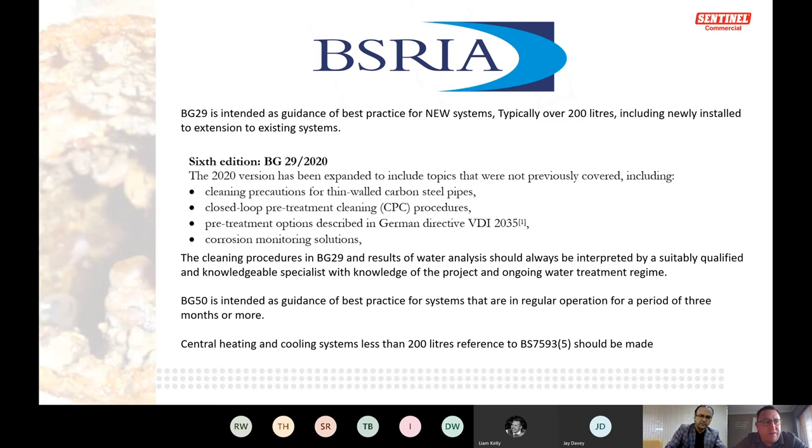VDI 2035 is more to do with demineralized water, pH balancing, and is a German directive requiring effective de-aeration. What we're looking at is chemicals and the standard approach in the UK. BG29 covers systems up to three months running, then BG50 takes over after that point. Systems under 200 litres — domestic type — are covered under BS 7593.